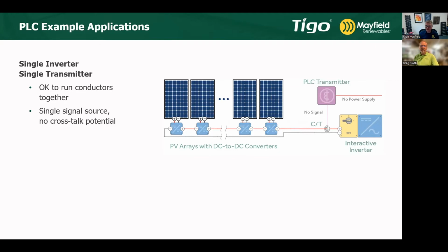In this case, and I can't speak for everybody, I'll speak to a Tigo specific thing, and Greg, please chime in here. The Tigo MLPEs are designed such that if they don't have the signal, their default is off. So they will not allow voltage, they will not allow current to pass through. The modules are still hot, the module input side is still hot, but the output side is not. This gets into commissioning as well, which I don't know if you want to talk about, Greg. But I won't speak to how other MLPEs actually do it, this is just the way Tigo does it.